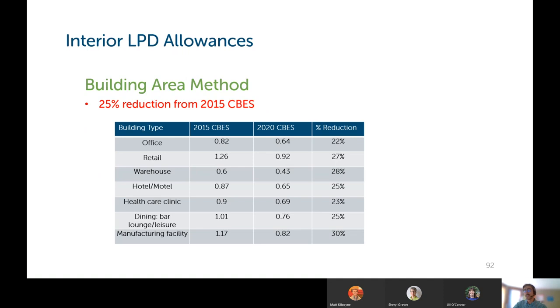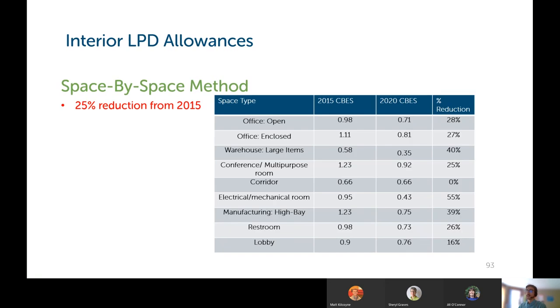The interior lighting power density allowances, for the building area method, are on average 25% lower than what the 2015 energy code allowed. So I've just listed a few of the pretty common building types here: office, retail, warehouse, manufacturing, healthcare, and bar or dining. And on average, those range, but are about 25% lower than the current code. If you're looking at the space by space method, it is similarly about a 25% reduction if you average out all the different spaces with the 2015 version.